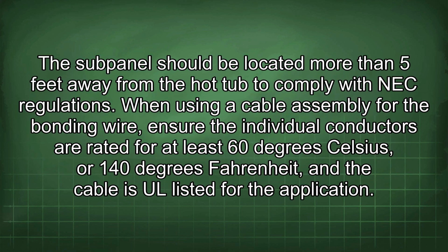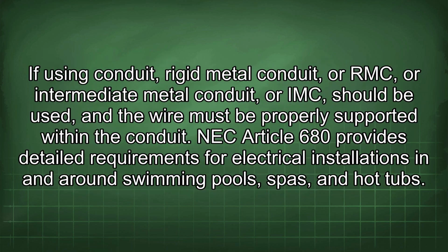The subpanel should be located more than 5 feet away from the hot tub to comply with NEC regulations. When using a cable assembly for the bonding wire, ensure the individual conductors are rated for at least 60 degrees Celsius or 140 degrees Fahrenheit and the cable is UL listed for the application. If using conduit, rigid metal conduit or RMC or intermediate metal conduit or IMC should be used, and the wire must be properly supported within the conduit.